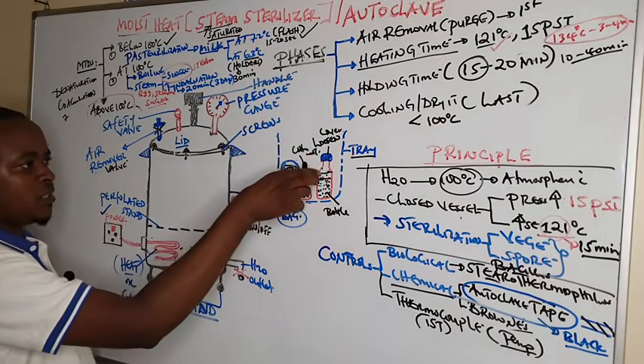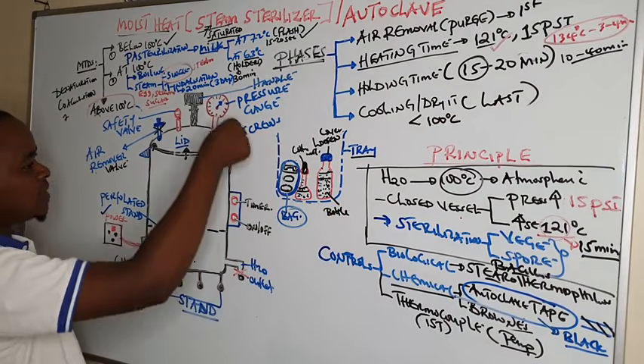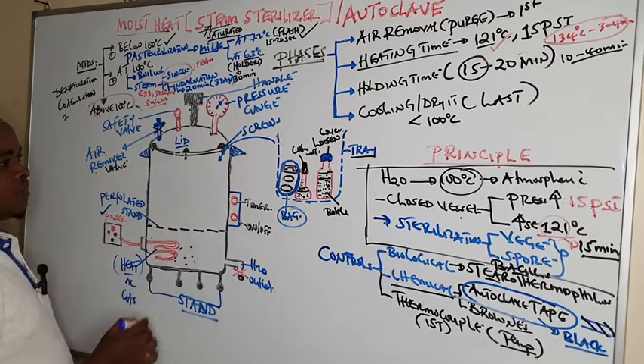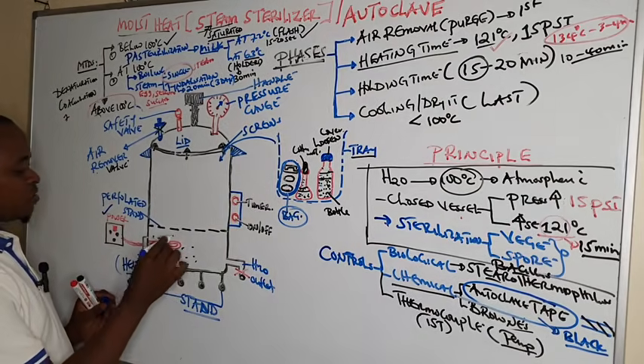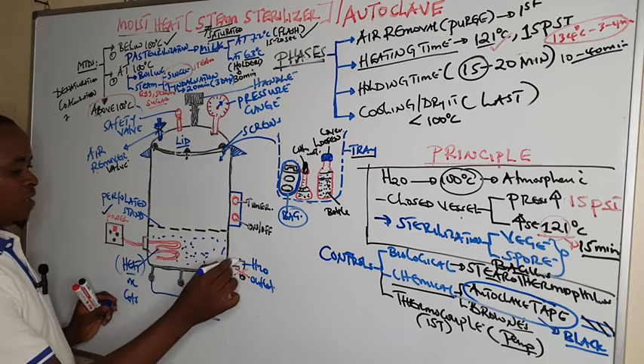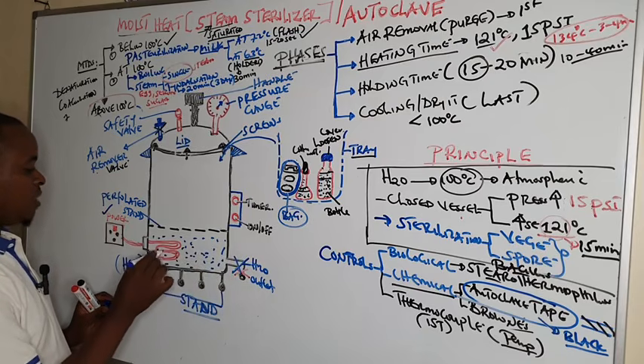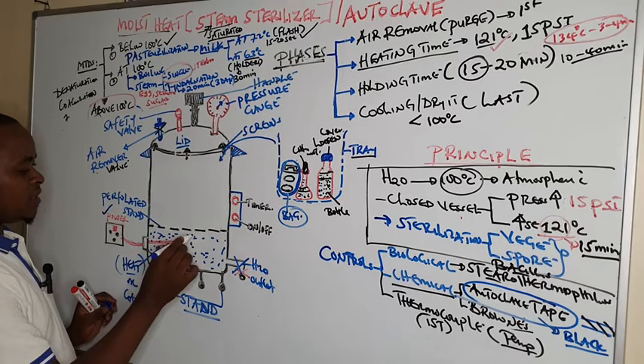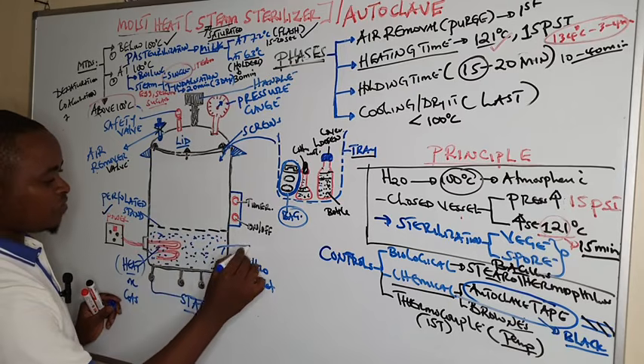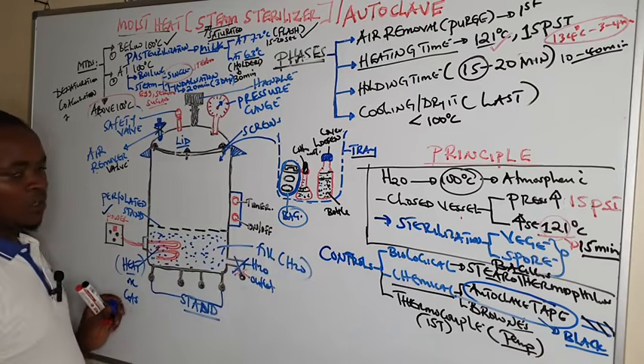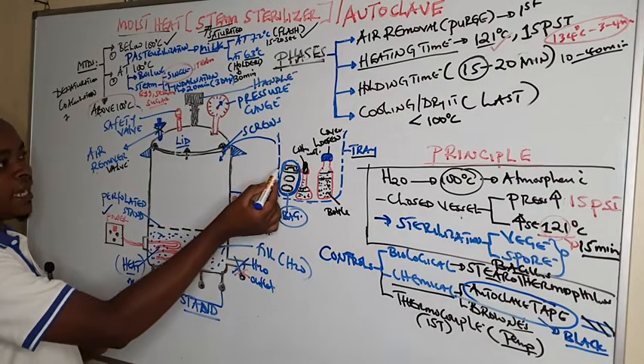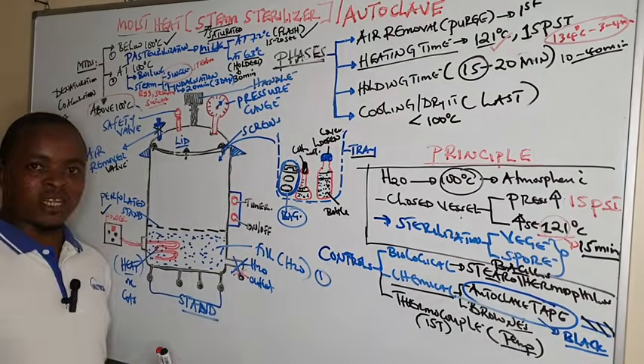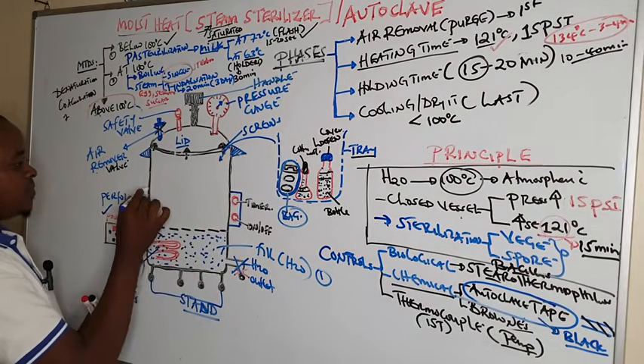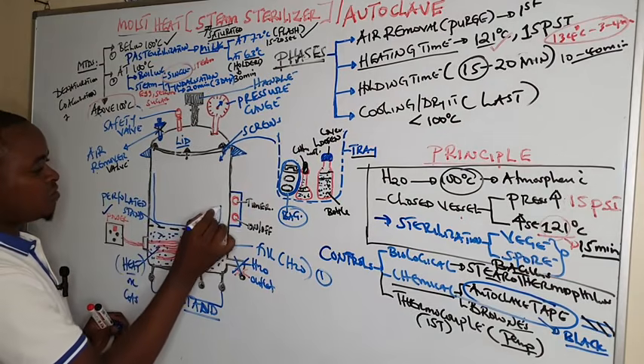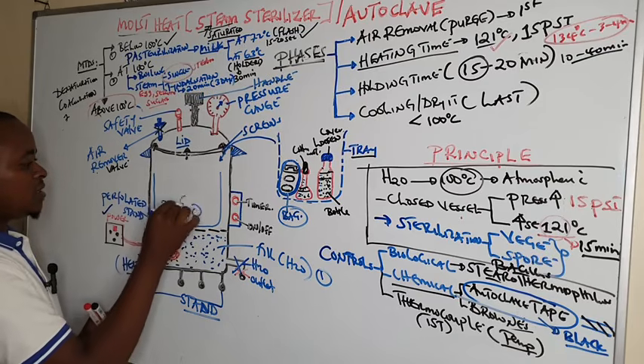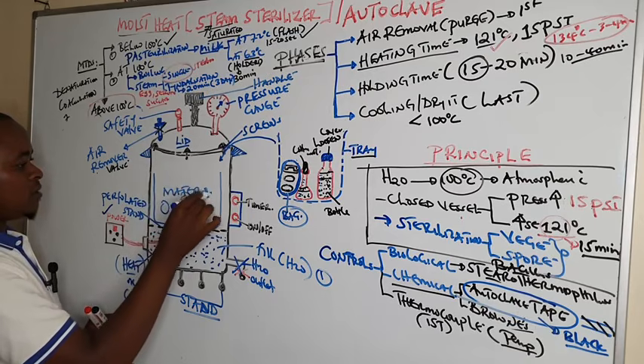After packing or loading the materials within the tray, we come and insert the tray. But before inserting the tray, we first fill the autoclave tank with water. When the outlet is closed, we fill it with water until the water covers the heater or the gas. So the first procedure is to fill the autoclave with water. Then you come and insert the loaded tray into the autoclave with the materials to be sterilized. These are the materials which we already loaded to be sterilized.